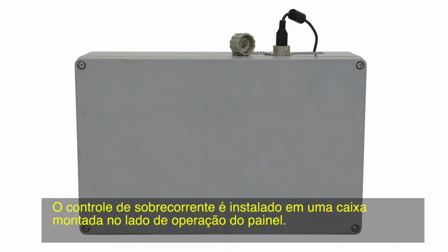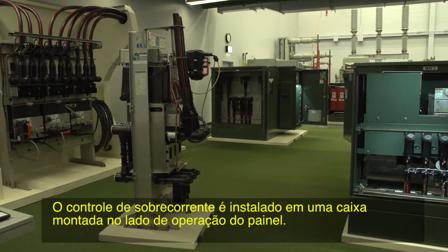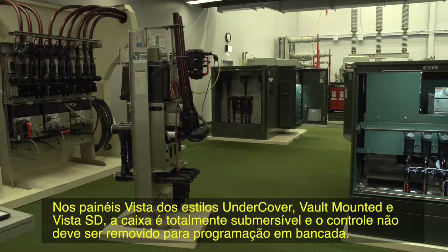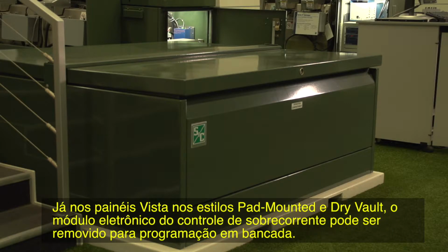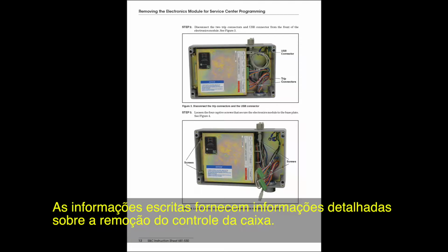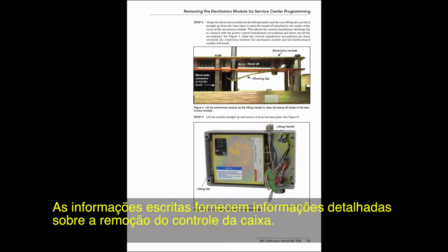The overcurrent control is housed in an enclosure mounted on the operation side of the switchgear. For undercover style and vault-mounted style Vista and Vista SD switchgear, the enclosure is fully submersible and the control should not be removed for bench programming. For pad-mounted and dry vault style Vistas, the overcurrent control's electronics module is removable for bench programming. The written instructions give a lot more information on removing the control from the enclosure.